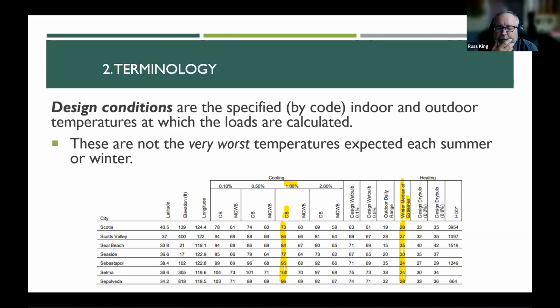So here on this table, we got Sebastopol. Sebastopol is in your guys' area, and it says, by the way, we use a number called the 1 percentile day. And what that means is 99% of the time, it's cooler than this number. But that also means that just less than 1% of the time, it's hotter than this. So when we pick a design temperature, we are by definition picking a temperature that's going to be exceeded 1% of the time.